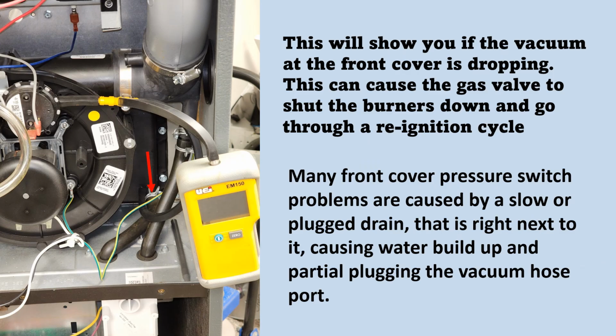This will show you if the vacuum at the front cover is dropping. This can cause the gas valve to shut the burner down and go through a reignition cycle. Many front cover pressure switch problems are caused by a slow or plugged drain that is right next to it, causing water buildup and partially plugging the vacuum hose port.